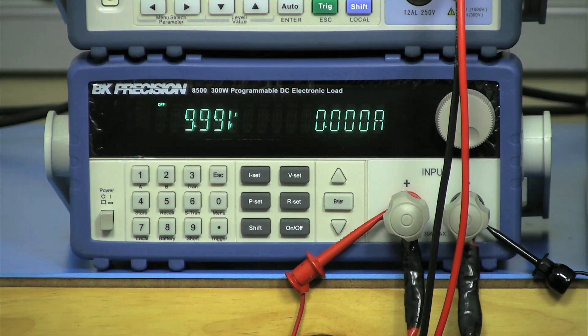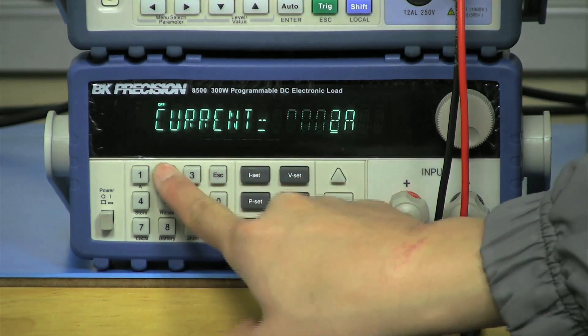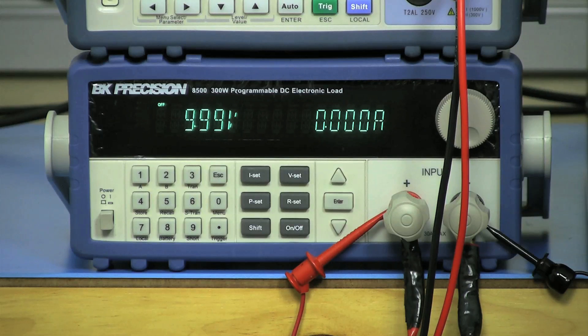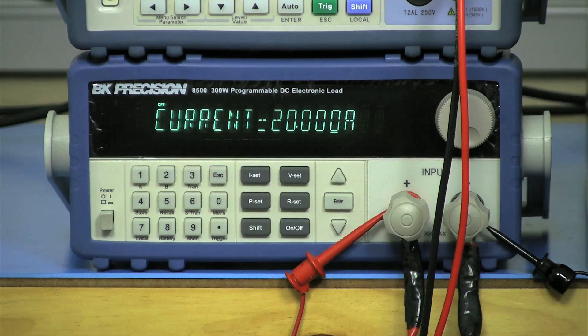Now I will set up the 8500 as a constant current load with 20 amps. Press the ISET button and type 20 and press enter to save. The load should be configured to sink 20 amps. You can press ISET again to verify.